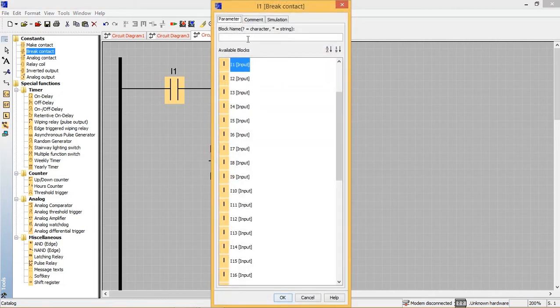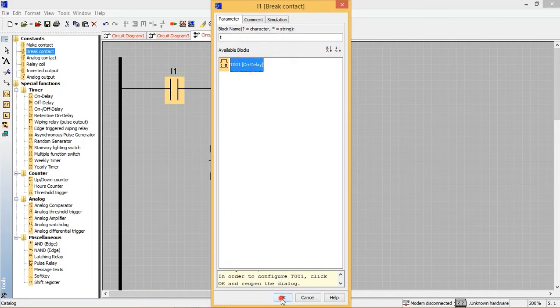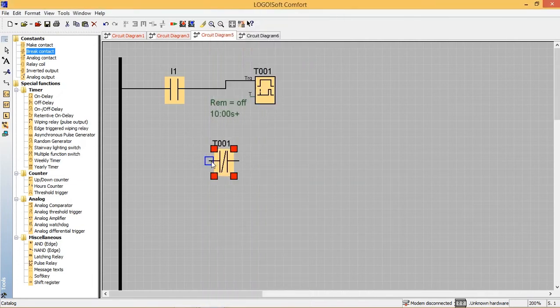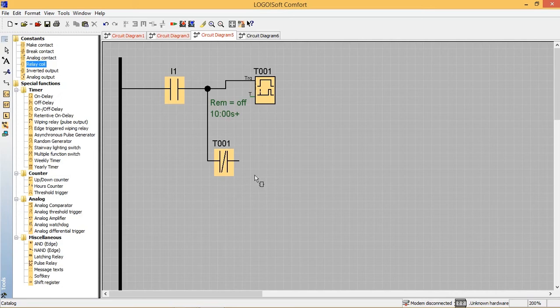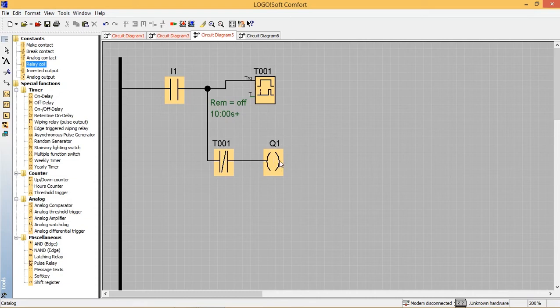Our condition is we need to turn on our output for the next 10 seconds, so I'm taking just the opposite — a normally closed contact — and taking the feedback of the timer. When you give input, the timer will start counting, but after 10 seconds its coil becomes high. So I have taken a normally closed contact and connected it to our output. After 10 seconds your output should be in off condition.